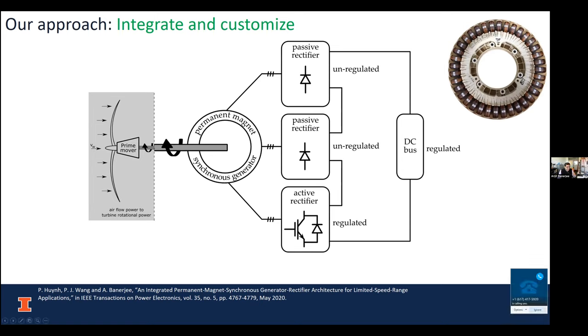These passive rectifiers are not ideal, and one reason for poor power factor at the input of these passive rectifiers is the capacitors at the DC link. If we can eliminate those capacitors, we will have much better power factor. In fact, what we achieve is around 0.95 or 0.96 power factor at the passive ports, even though it's run by passive diodes.